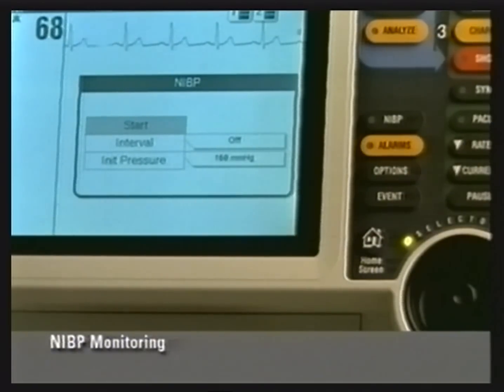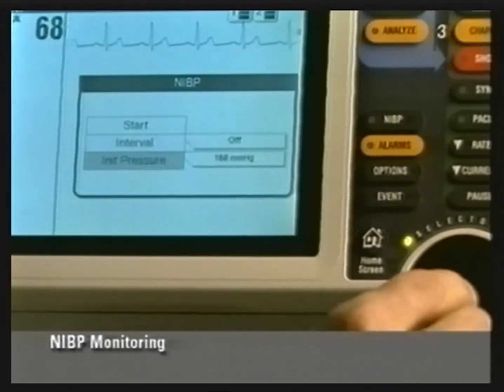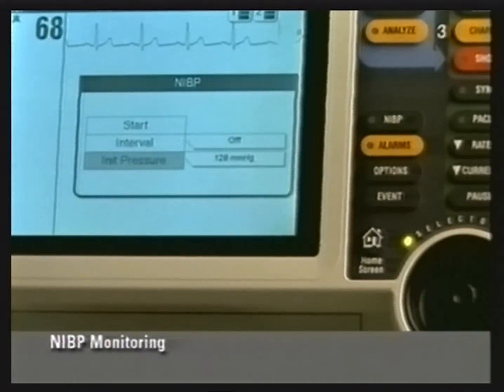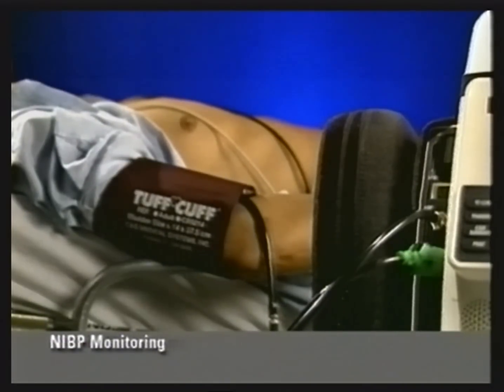If you know the patient's blood pressure and need to adjust the inflation pressure, select the NIBP area on the screen. Select initial pressure and choose the appropriate inflation pressure. Be sure not to select an inflation pressure that is below the patient's systolic pressure. Doing so may cause the NIBP monitor to reinflate and take longer to obtain a reading. This could also be very uncomfortable for the patient.